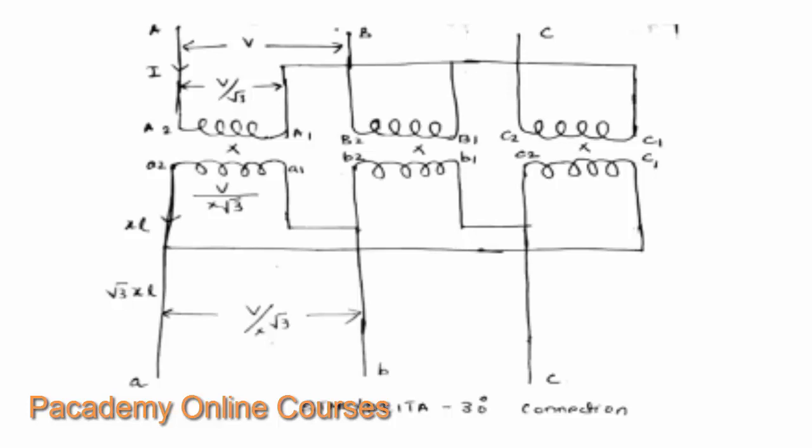the line-to-line voltage at the star end will be V, but the voltage between the phase or the windings, individual windings, will be V by root three. And there is a reduction in the voltage by a margin of root three, which will reduce the insulation cost of the windings.